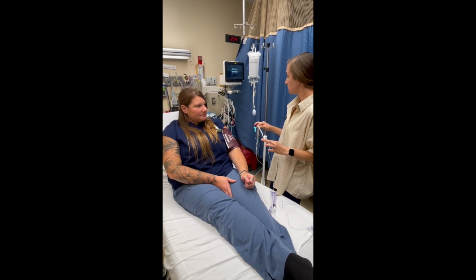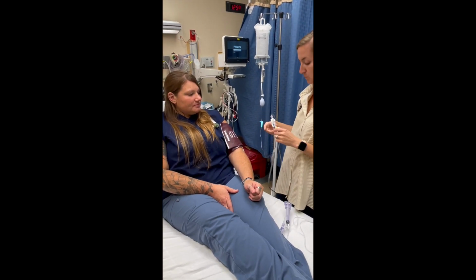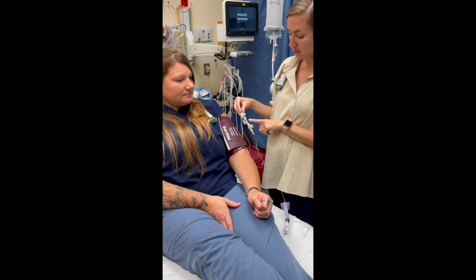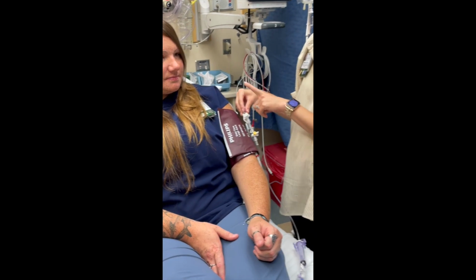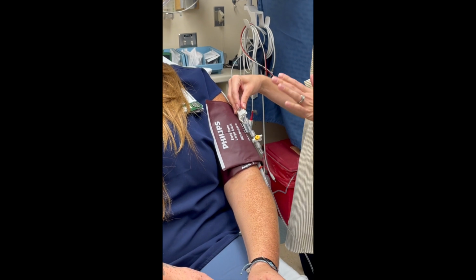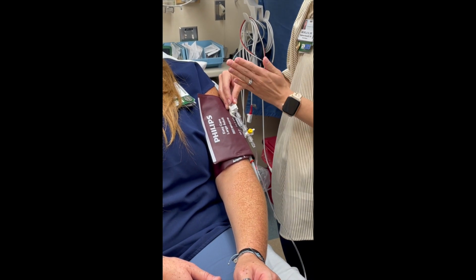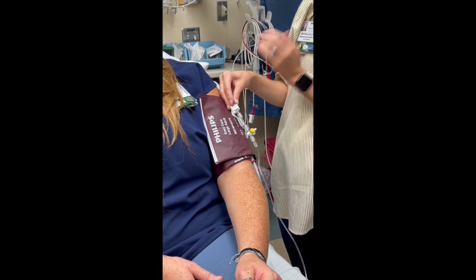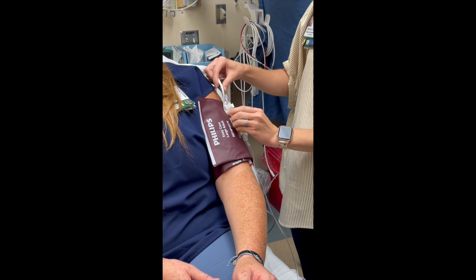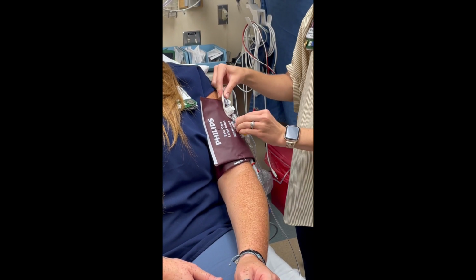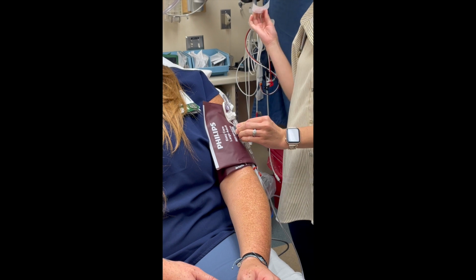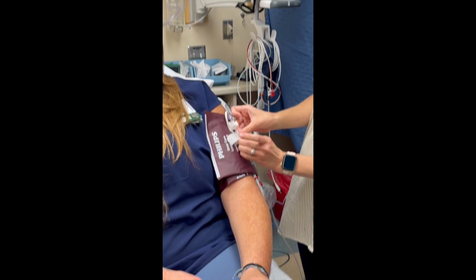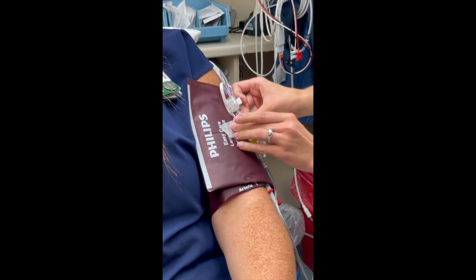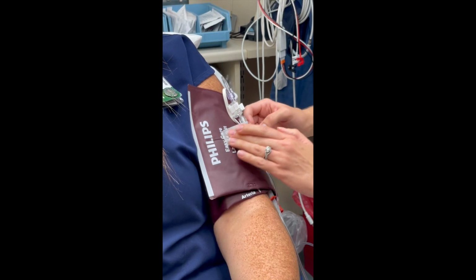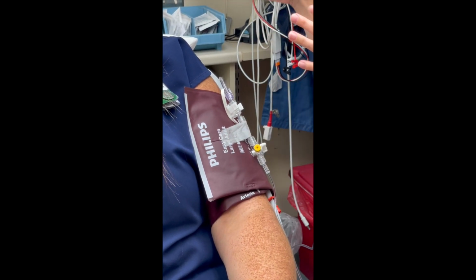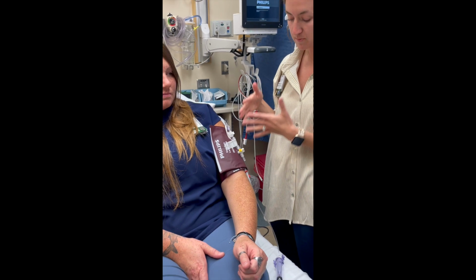Next, what we're going to do is zero our tubing. We want to align our transducer with the patient's phlebostatic axis, which is roughly mid-axillary line, fourth intercostal space. Some departments have holders. If you don't have a holder, you can simply use a piece of tape across the transducer to a blood pressure cuff or to their arm. Never tape this tubing to the bed. It should always be with your patient.